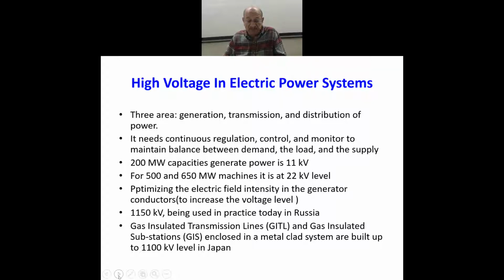And then we need larger machines to be installed in the generating stations. Earlier we used to have even 5 megawatt considered to be a big machine, 5 or 10 megawatt. But today, 650 megawatt generators are being produced in our country. And the level of voltage at which this power is produced in the machine, that is the synchronous generator, we call it, is at 22 kV only.